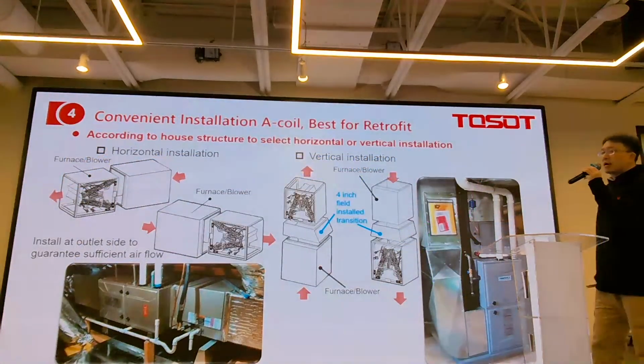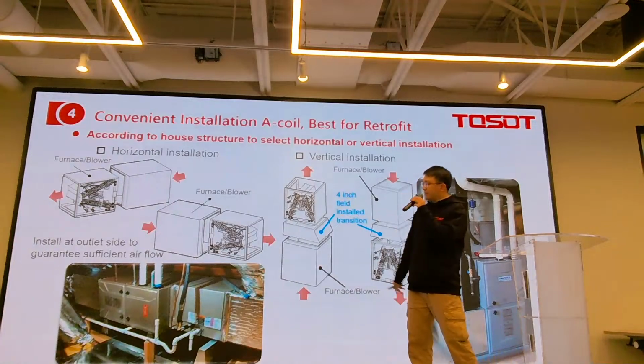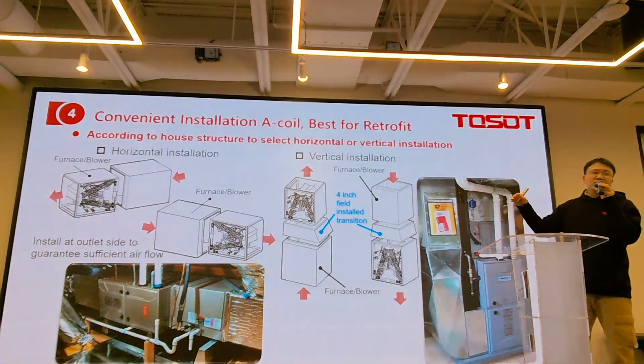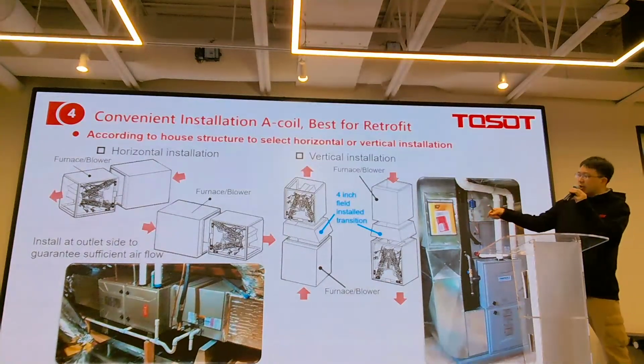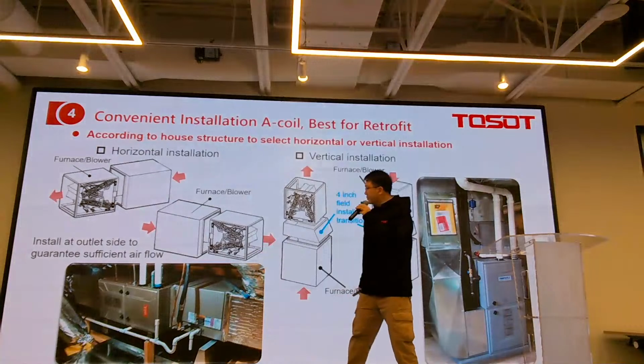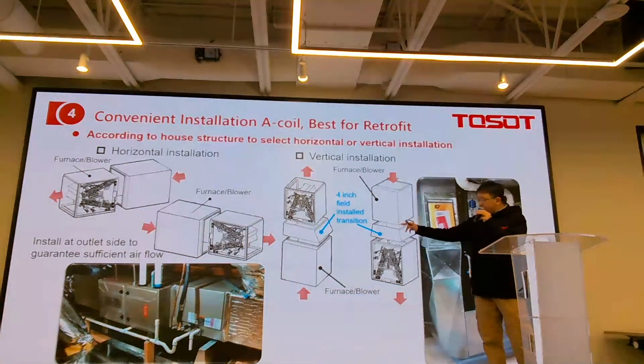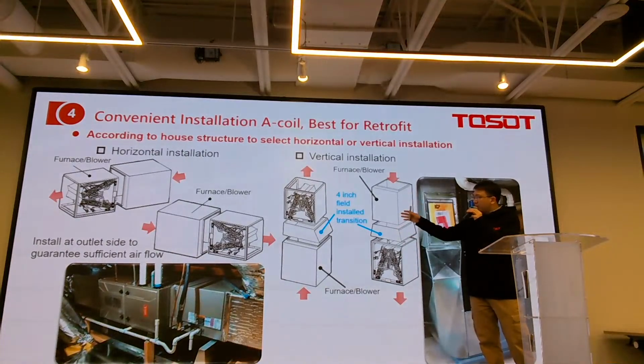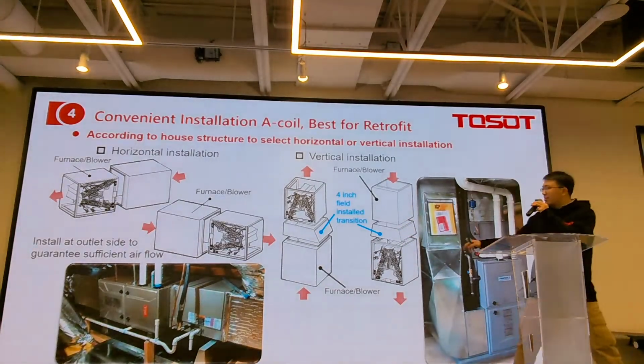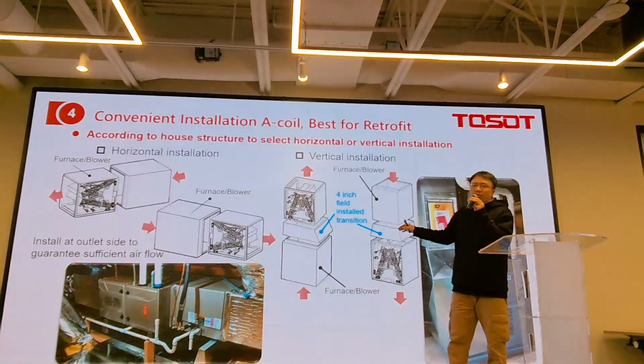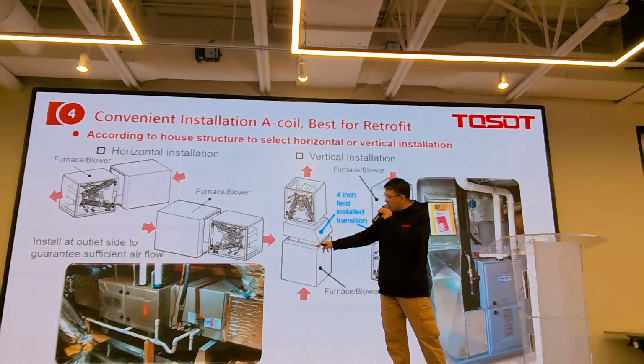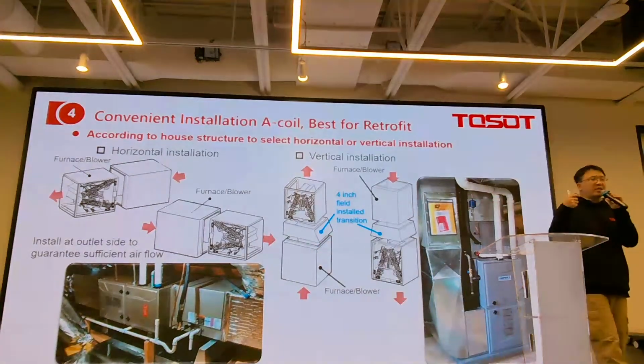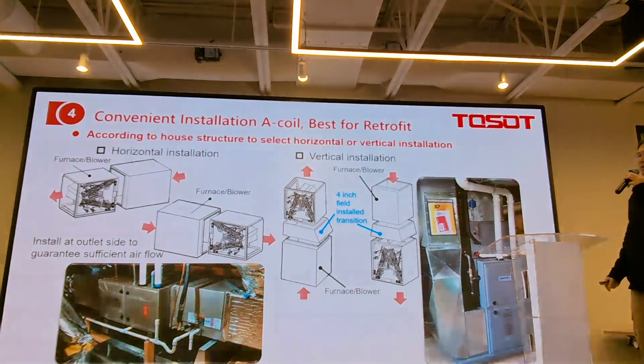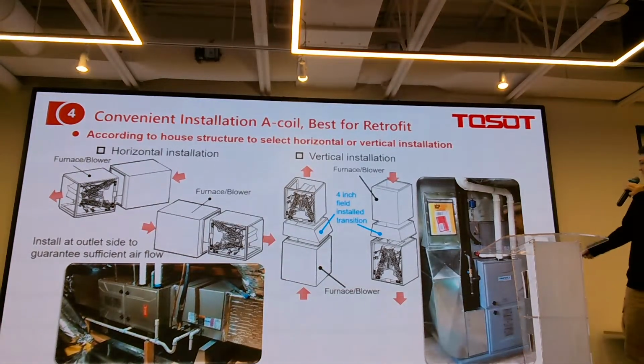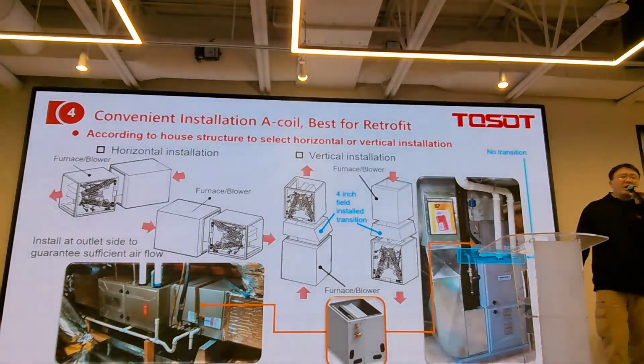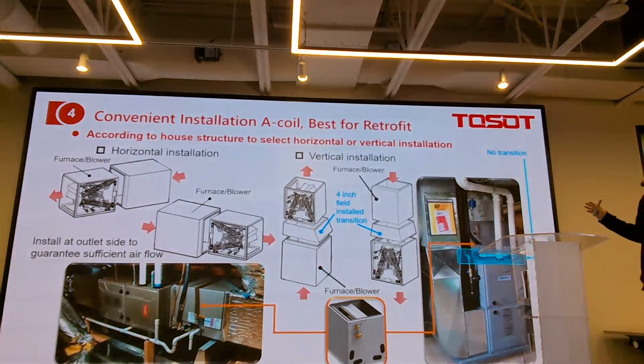And for the furnace and the A coil, we also support all the directions, either horizontal or vertical. Just like what I said, pay attention to the drain pan. Always guarantee the drain pan is at the lower side. For the upflow or vertical installation, we only recommend to install this transition. The problem is due to the heat. If it heats up too much, we are afraid the drain pan is not sustainable. But on your sample, you didn't install it. You can also find that there's no transition. We just recommend it.